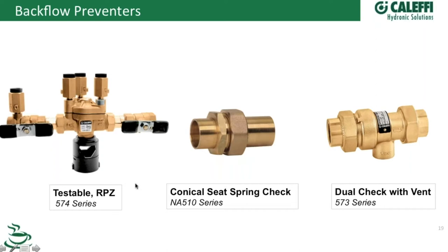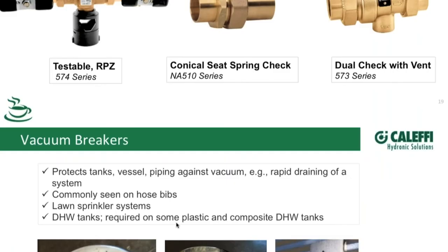This check valve — I like to see this type of check valve used in hydronic applications. This is a conical seat spring type of check valve. It gives you a near bubble-free seal. So if you want to make sure you don't have ghost flow in some of your zones, this is a union type of check valve we offer for hydronics that has a nice tight seal with a spring check mechanism.